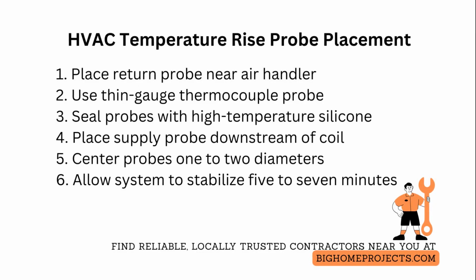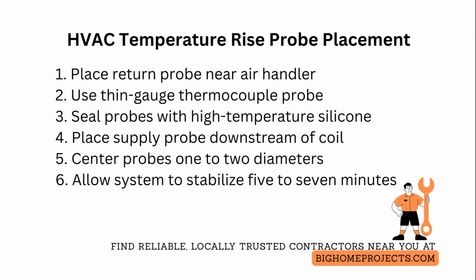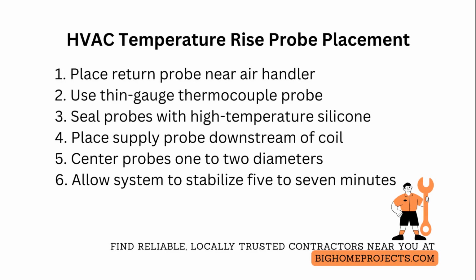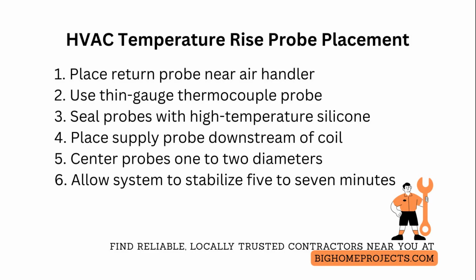Place it in the center of the supply duct cross-section at least 1 to 2 duct diameters away from elbows, takeoffs, or transitional fittings to get a representative mixed supply temperature. Align both probes at roughly the same axial plane and vertical position relative to duct centerline when possible, so the delta temperature is between airstreams that have traversed similar flow paths.